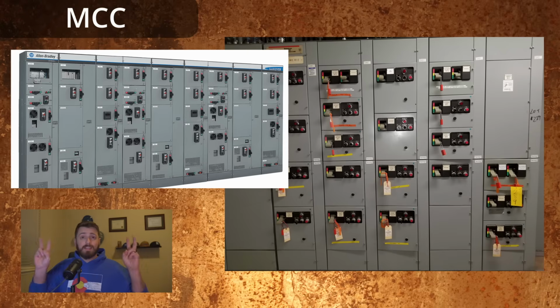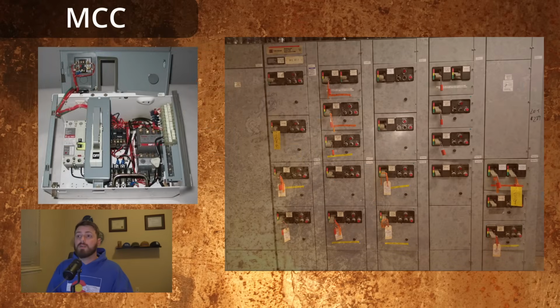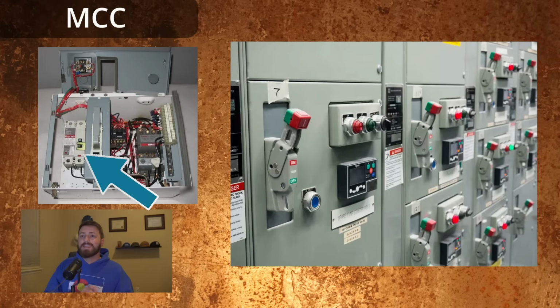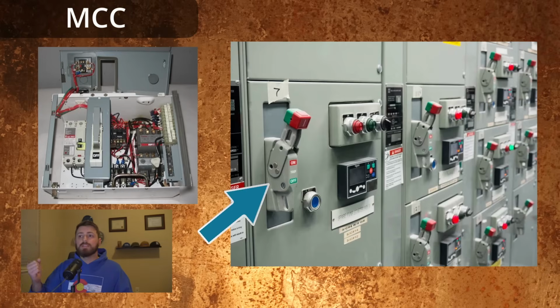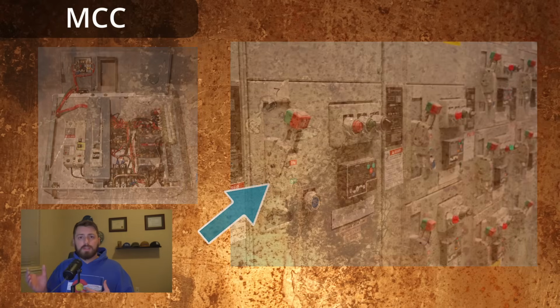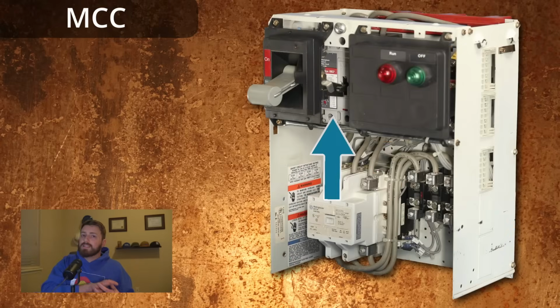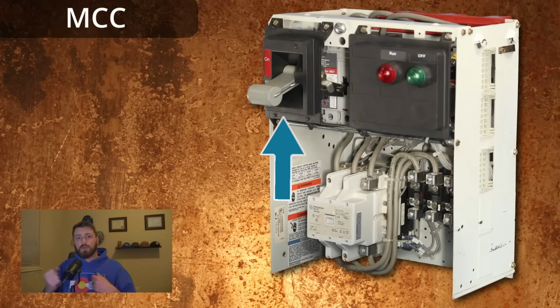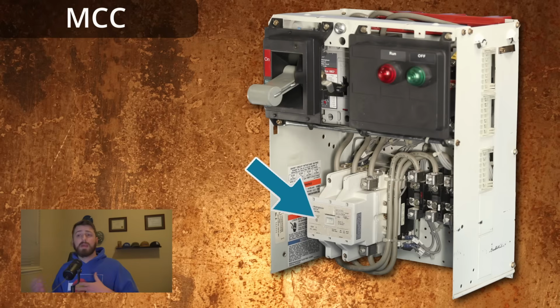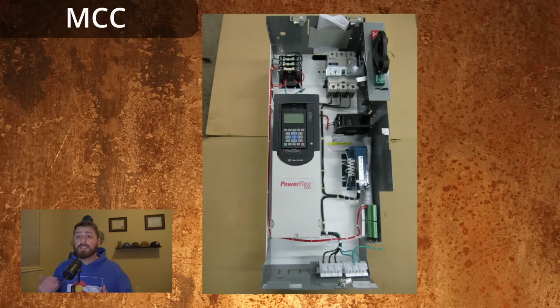MCCs may contain a main section where it's got a big main circuit breaker. Typically, it's a larger molded case circuit breaker, but it can be a larger insulated case or power circuit breaker. They'll typically have many motor control buckets, as we call them, where a smaller breaker is actually hidden inside and a separate manual disconnect switch is seen on the front of the gear for each bucket. So you've got a breaker doing the overcurrent protection inside that's not really accessible, and then you've got a manual disconnect switch for starting and stopping the load. These can also contain additional components like automatic contactors, variable frequency drives, and soft starters.